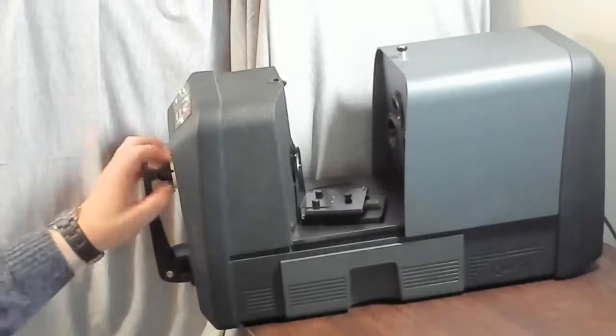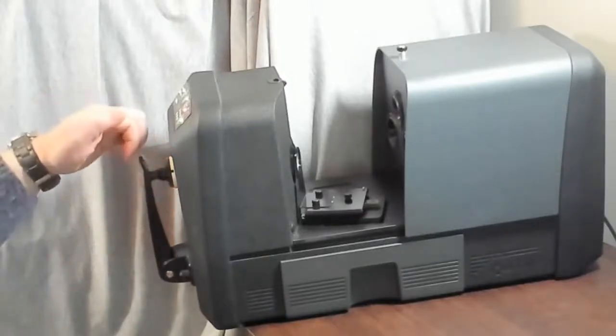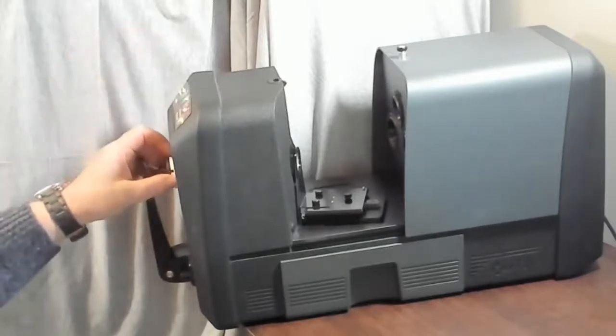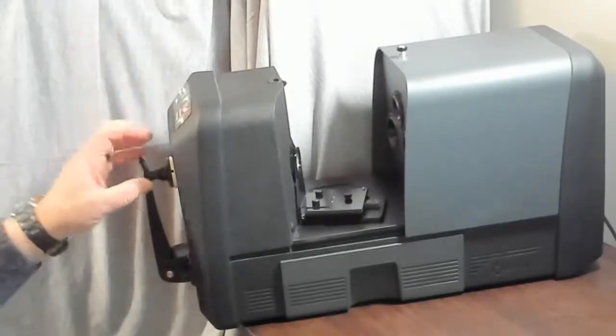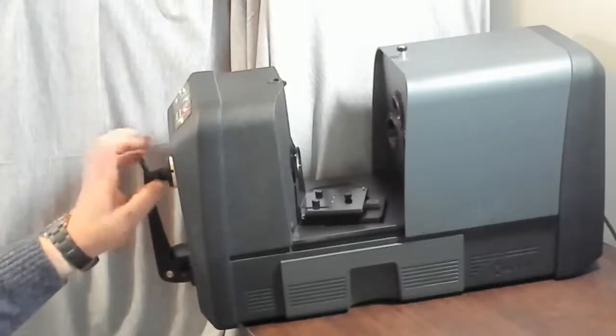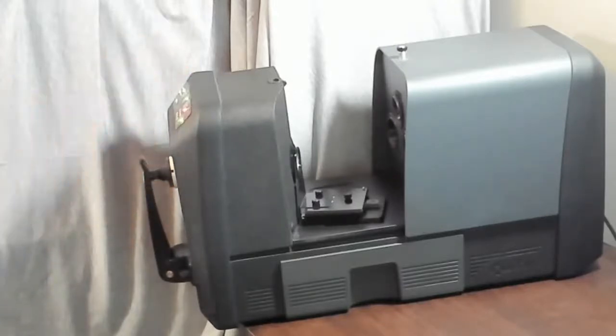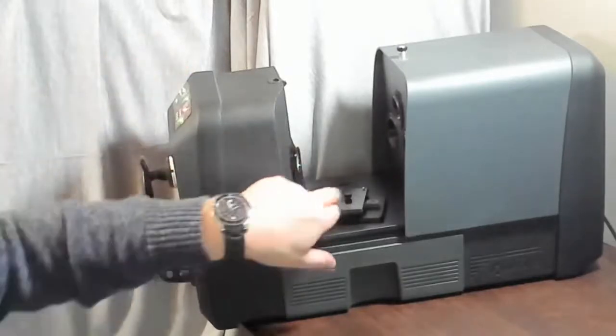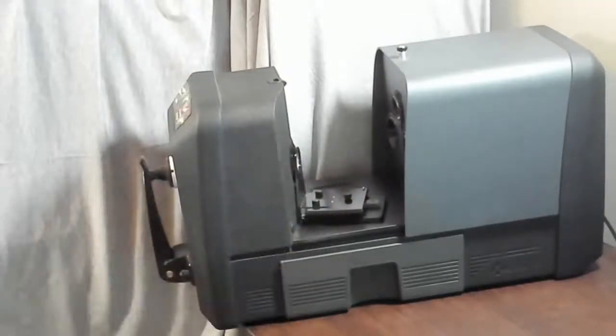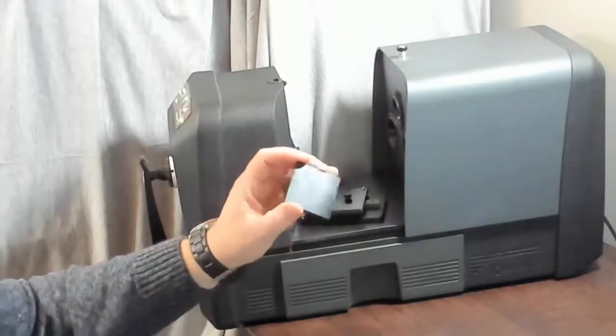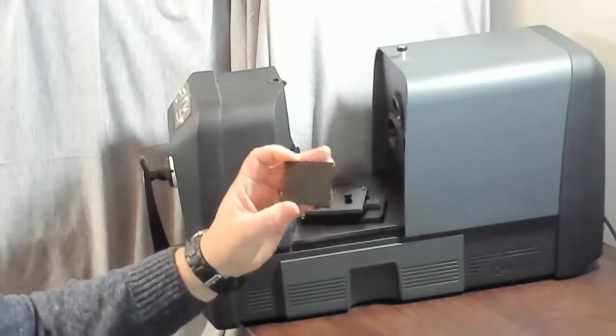Now, for the vast majority of my transmission measurements, I'm never going to move this, and its purpose is not to be measured like we would in reflectance, but its purpose is to complete the sphere. So between the aperture plate and that calibration white, we're completing the sphere to try and direct all the light back out through the sample that I'll be measuring here. So we've got one more piece that we'll use in a minute when we calibrate, and that's this black plastic. That's to block the light.